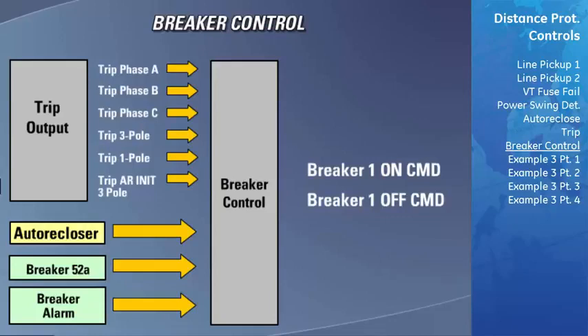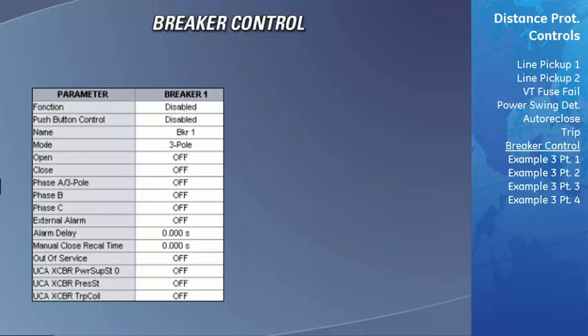There is the ability to control two breakers with the D60, and that is why the number 1 is listed in the breaker control operand seen here. The only step the user must now perform is to assign the breaker1 on command to the contact output that closes the breaker, and assign the breaker1 off command to the contact output that trips the breaker.